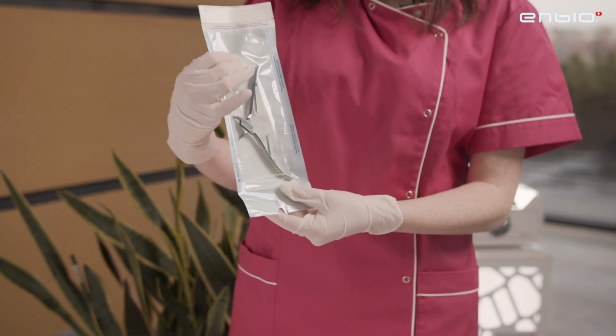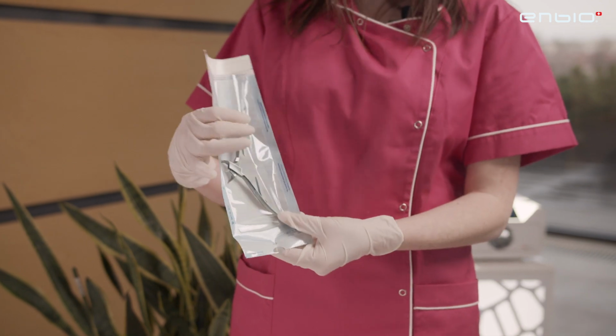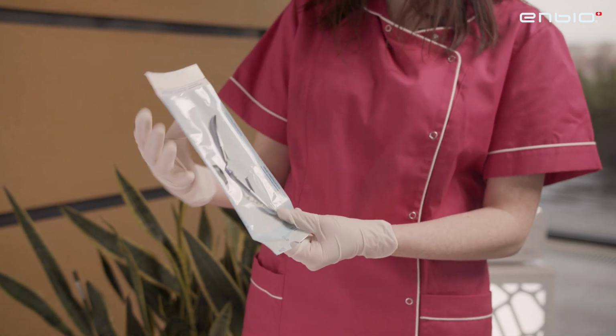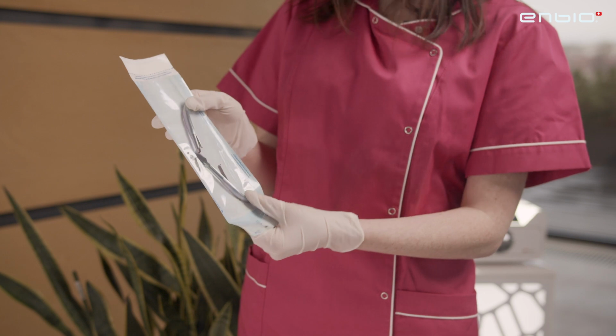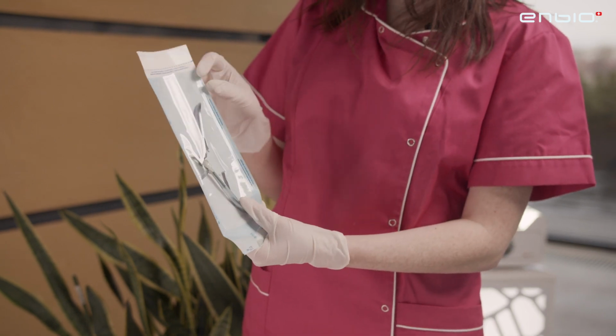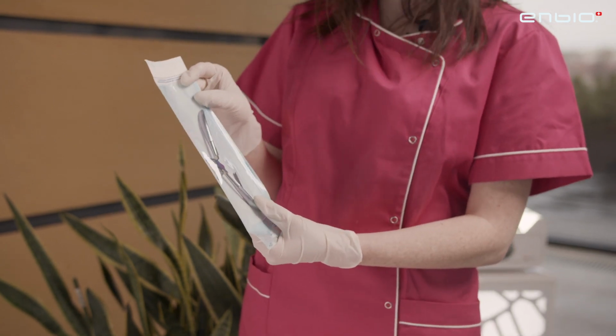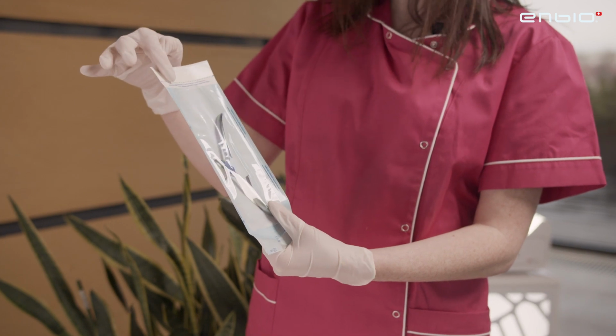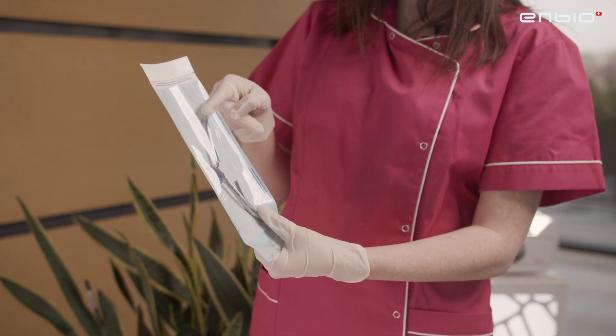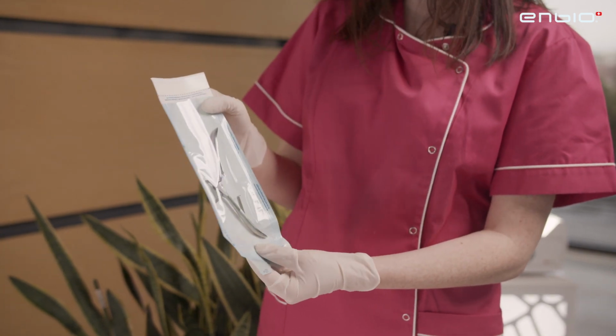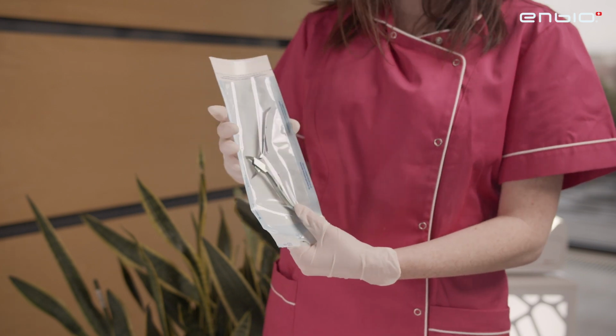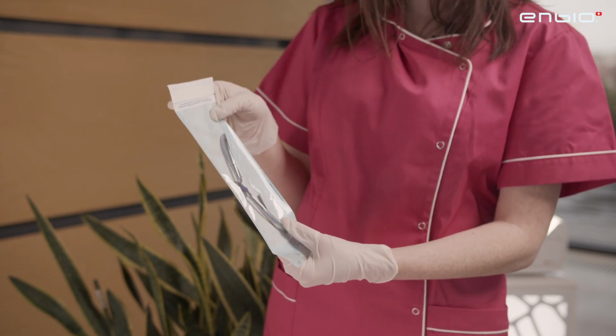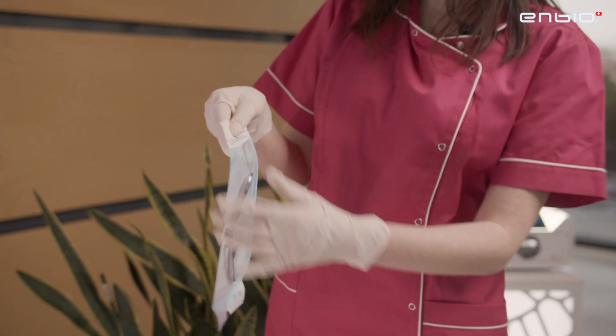I have selected a sterilization pouch that corresponds to the dimensions of my tool. It is important to remember here to allocate at least 3 centimeters between the discontinued line and the position of the tool inside the pouch, because during the sterilization process, the pouch can swell.